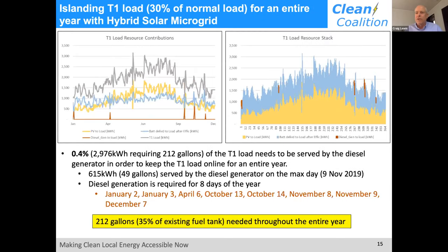So what you actually design for, in their case, is that critical loads are 30% of their loads. If we only guarantee that 30% of loads stay on 100% of the time, the diesel amount needed is only 0.4%. Looking at the right-hand chart, you'll see just a couple of splotches of brown—those are the only times you need to turn those dirty, stinky diesels on. In fact it's so little that we can design the diesels out entirely, because we can turn a few loads off as needed to make up that 0.4% the diesels would otherwise carry. Only 30% of the site's loads are critical, so only that 30% needs to be on 100% of the time. The other loads can run as solar energy is available.